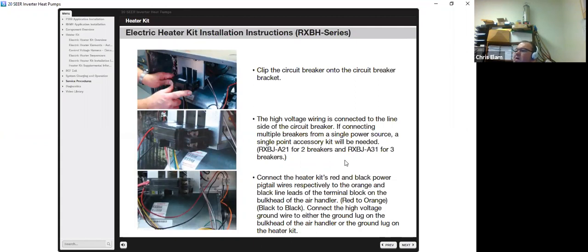Right here, the high voltage wiring is connected to the line side of the circuit breaker. If connecting multiple breakers to a single source power. You will need a single point accessory kit, which is the RXBJ-A21 for 2 breakers and the RXBJ-A31 for 3 breakers. You'll have to attach the heater kit's red and black power pigtail wires, respectively, to the orange and black leads of the terminal block. On the right-hand side towards the back, you'll see basically 4 screws. You have the black and orange at the bottom, and you take the red and black over to it, and green at the top. Red should go to orange, and black should go to black. Connect the high voltage ground wire to either the ground lug on the bulkhead of the air handler or the ground lug on the heater kit.